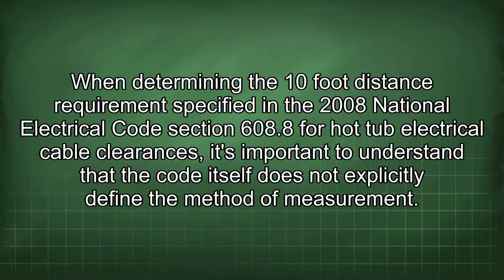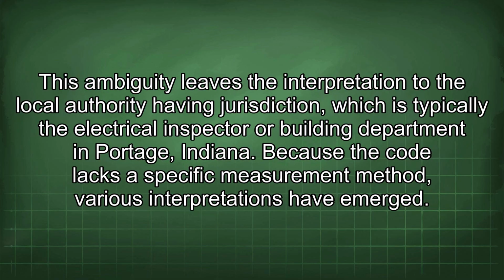When determining the 10-foot distance requirement specified in the 2008 National Electrical Code Section 608.8 for hot tub electrical cable clearances, it's important to understand that the code itself does not explicitly define the method of measurement. This ambiguity leaves the interpretation to the local authority having jurisdiction, which is typically the electrical inspector or building department in Portage, Indiana. Because the code lacks a specific measurement method, various interpretations have emerged.